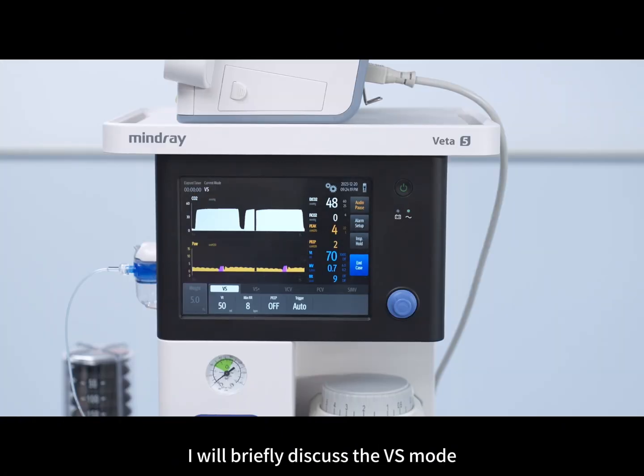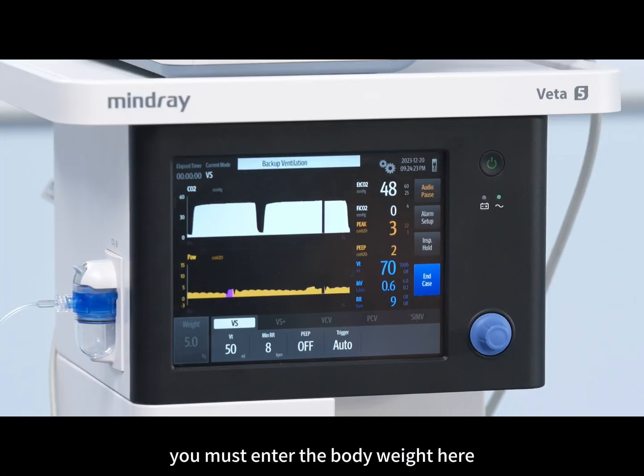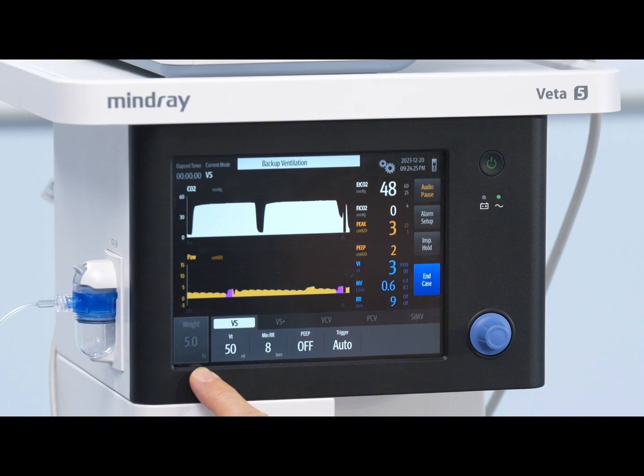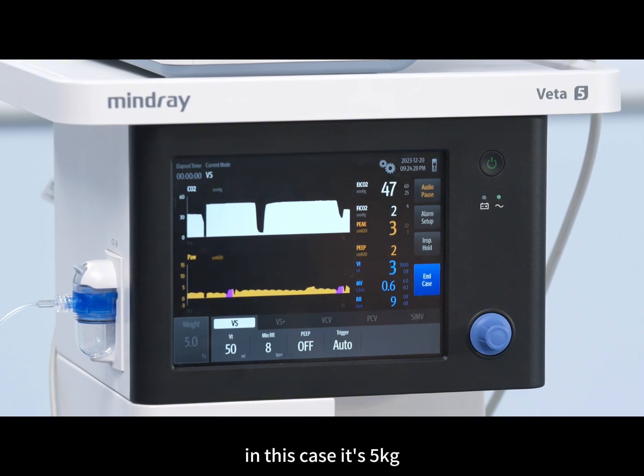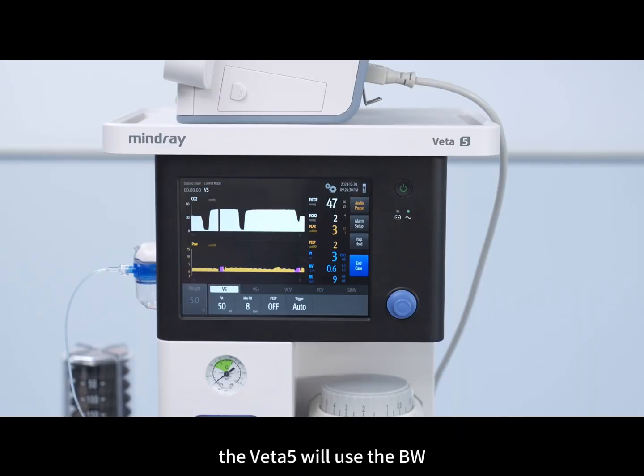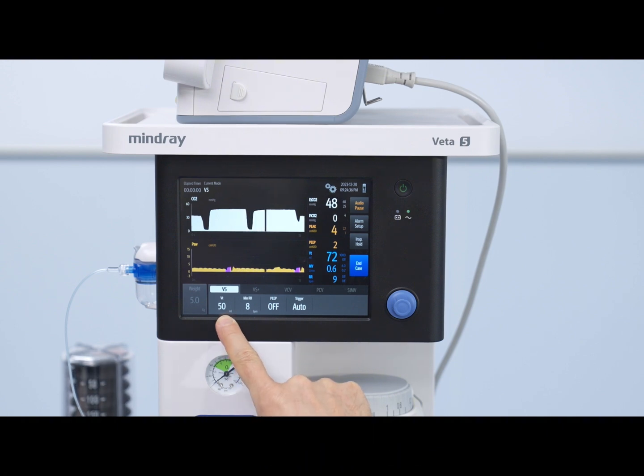Now I will briefly discuss the VS mode. Before starting a case, you must enter the body weight here. In this case, it's 5 kg. The Veta 5 will use the body weight to calculate the initial tidal volume, which appears here.